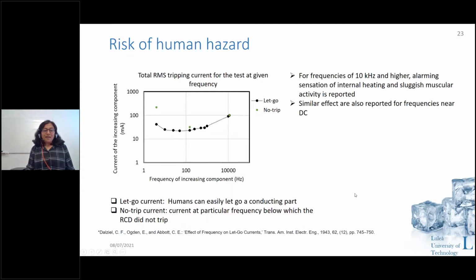So for this, I came across a very old paper by Dalziel, and at that time he had done measurements with people in 1943, and there's a curve of let-go current at different frequencies, at which people can let go of their own, without any external help, if they are clutching a live conductor. So we made a comparison of some of the non-tripping currents. I mean, the minimum current at which no RCD was tripping. We could keep going higher and they wouldn't trip.